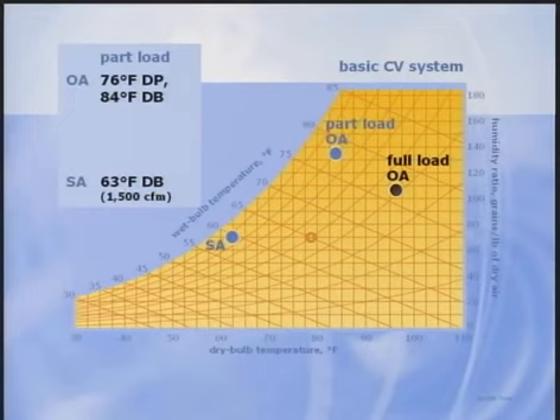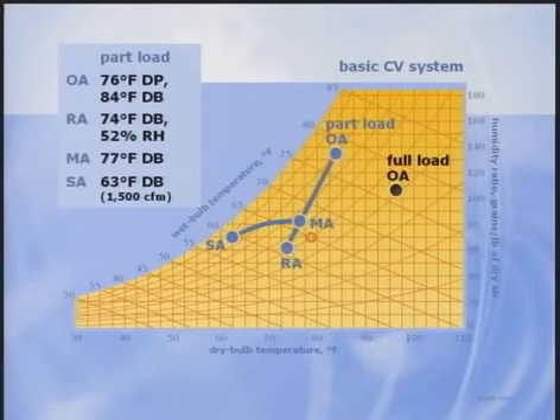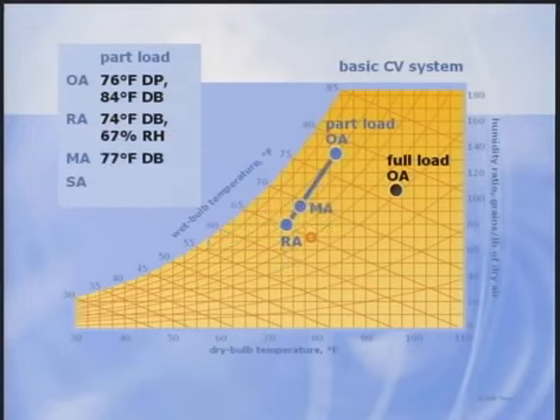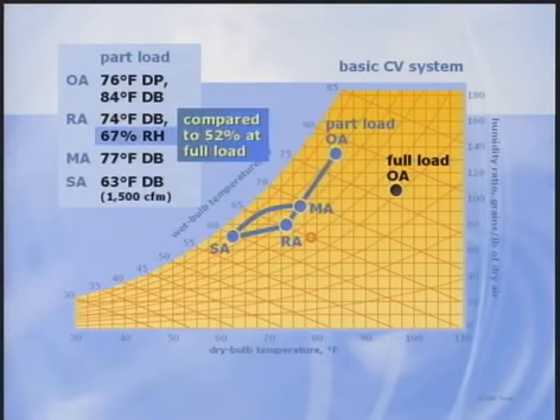design. We start our analysis by assuming a return air condition from the zone to find the mixed air condition. Since lower sensible load requires less cooling capacity, the constant volume system delivers warmer and wetter supply air. The resulting zone humidity is much higher than we initially assumed, so we iterate until the resulting return air condition matches the condition initially assumed. Relative humidity rises to 67%, so this system in this climate doesn't comply with standard 62.